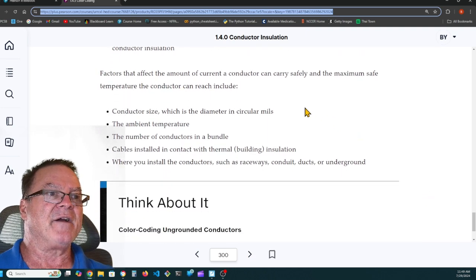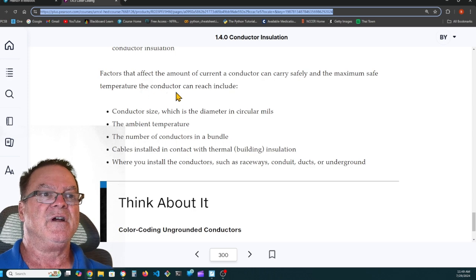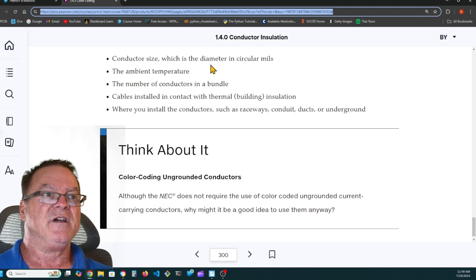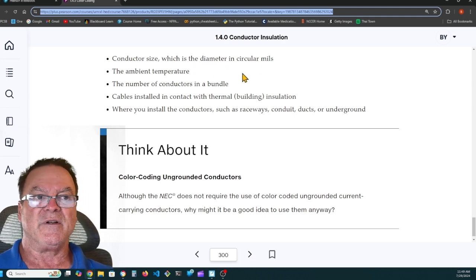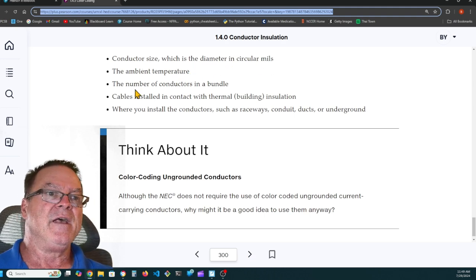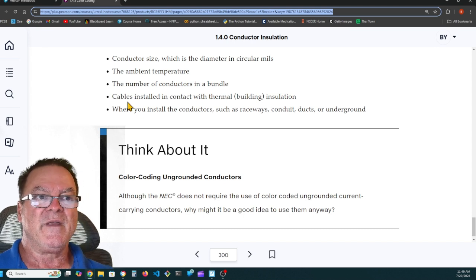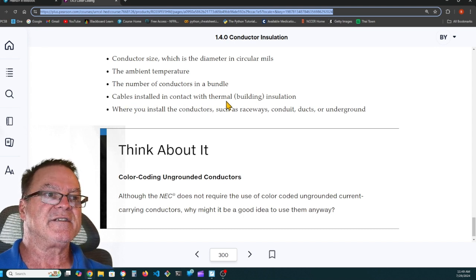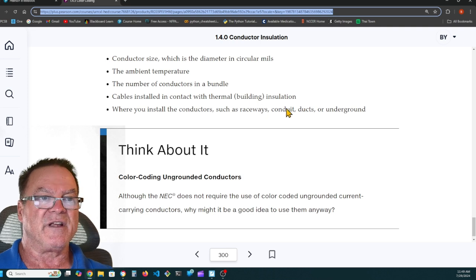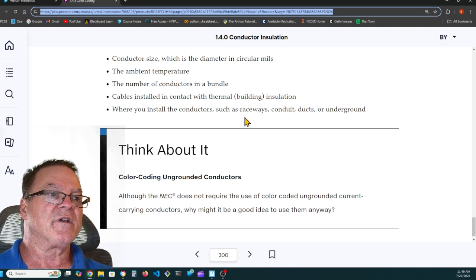Factors that affect the amount of current a conductor can carry safely at the maximum safe temperature the conductor can reach include the conductor size, which is the diameter in circular mils, the ambient temperature, the number of conductors in a bundle, the cables installed in contact with thermal insulation, and where you install the conductors, such as raceway, conduit, ducts, or underground.